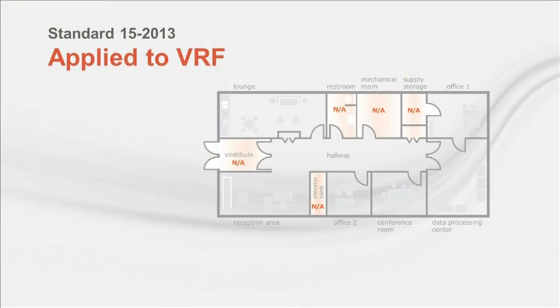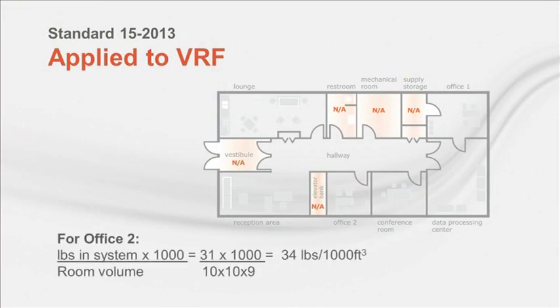Returning to our example building, the smallest room served by the system is Office 2. Using our estimated system refrigerant quantity of 31 pounds, the room volume of Office 2 yields a refrigerant concentration of 34 pounds per 1,000 cubic feet. This exceeds the RCL of 26 for our application, so it would not be permitted. The conference room is the next smallest room served by the system. The refrigerant concentration for this room is 24.6 pounds per 1,000 cubic feet. This meets the RCL requirement, but it doesn't provide any tolerance in the event that the actual charge exceeds the estimated charge.